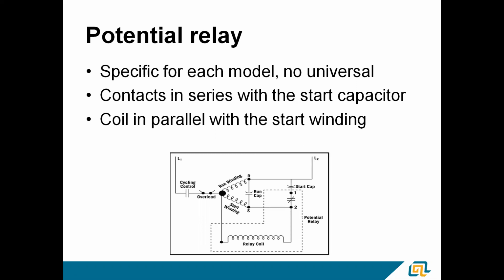If you notice, the contacts right here are normally closed, and they're in series with that start capacitor and the start winding. So when those contacts open, we're no longer going to have a connection from the start capacitor to the start winding. The coil of the relay right here is in parallel with the start winding. So it will get energized at the same time as the start winding, open that relay, and drop the start capacitor out of the circuit.